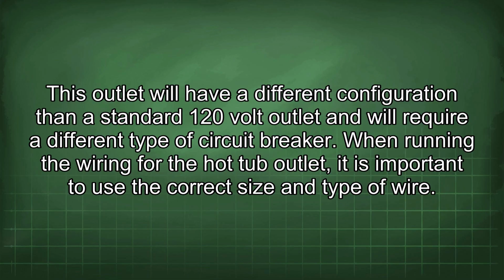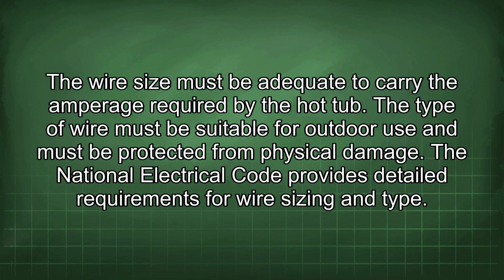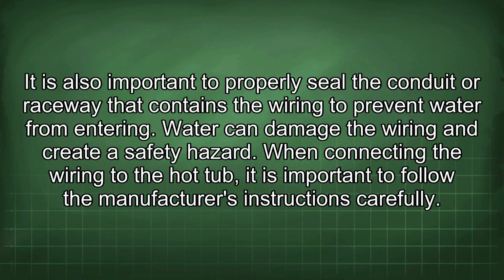of wire. The wire size must be adequate to carry the amperage required by the hot tub. The type of wire must be suitable for outdoor use and must be protected from physical damage. The National Electrical Code provides detailed requirements for wire sizing and type. It is also important to properly seal the conduit or raceway that contains the wiring to prevent water from entering. Water can damage the wiring and create a safety hazard.